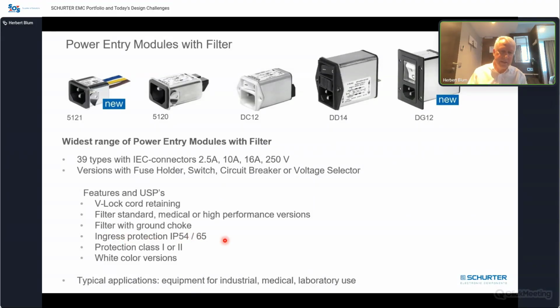That means they can be IP54, IP65 sealed, so waterproofed connectors, and protection class 1 or 2. Most of them are class 1, it's clear, with ground connector. Class 2 is without ground conductor. White color version, as you can see here on the picture, is more specially made for medical applications, where everything needs to be clean.